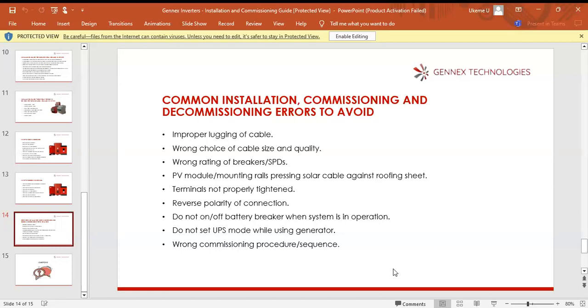If a terminal is not properly tightened, there will be heating, like at the battery terminal, the terminals of circuit breakers, or the terminals of the inverter itself, like the input battery terminals of the inverter or solar input. All these terminals are very important to be well tightened to avoid malfunction or misbehavior. It could damage the system. It can turn into poor power quality. Meanwhile, the quality of power coming from the grid is okay, but when it gets to where the inverters are installed, because of all these little errors, it will cause damage and misbehavior from the inverters.